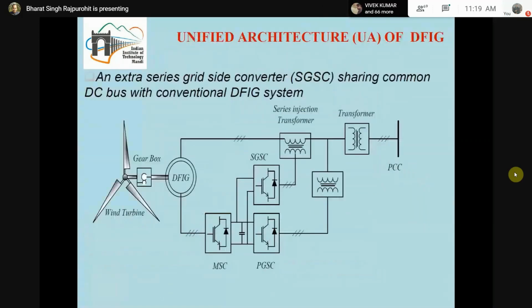And now some researchers have also suggested a third converter known as the series grid side converter, which is shown in this diagram. It utilizes the same DC link voltage but injects a voltage in series between the stator and the grid. This series voltage, when injected, is able to provide series compensation for the operation of the DFIG.